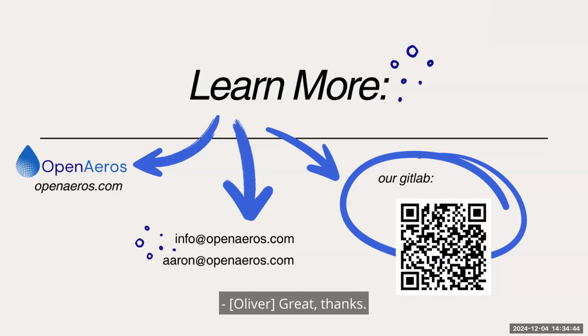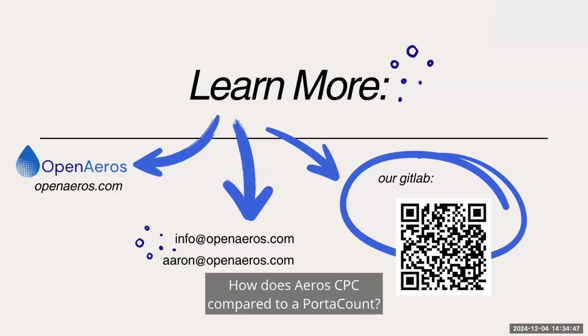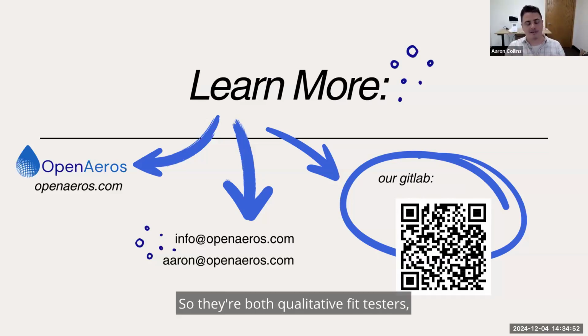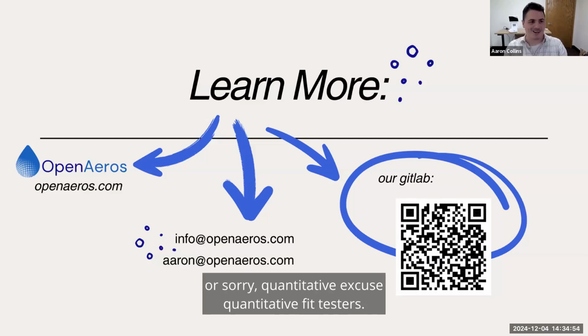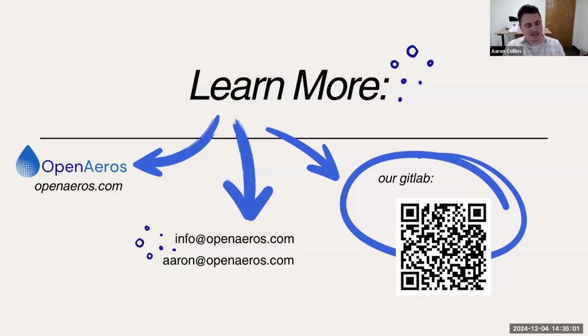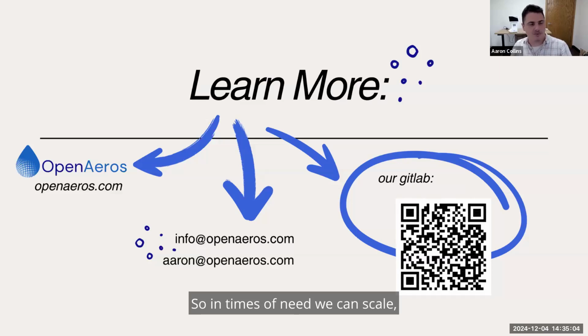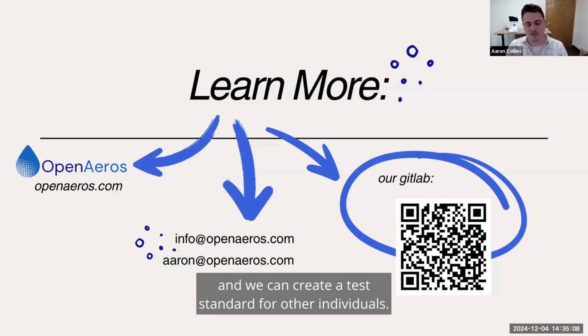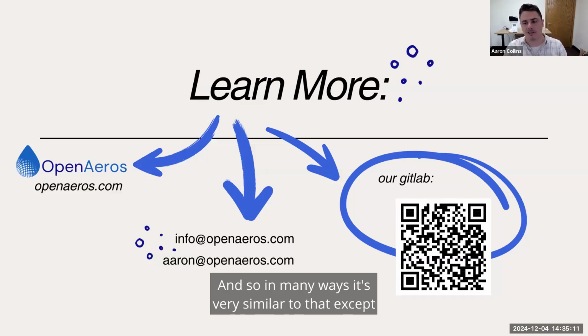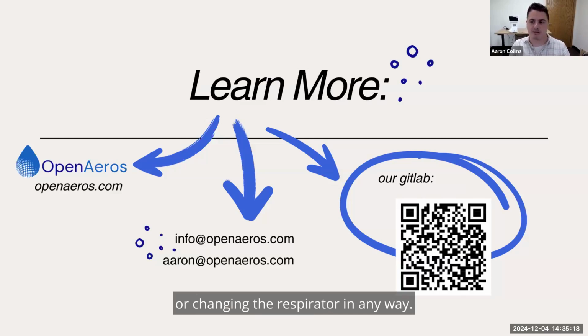How does the Aeros CPC compare to a PortaCount? They're very similar. They're both quantitative fit testers, so they measure the particle concentration inside and outside. The big advantage to ours is that it's a lot lower cost. It's also open source, so in times of need, we can scale, other manufacturers can produce them, and we can create a test standard for other individuals. It's also different because of this new probe technology, which allows you to do it without modifying or changing the respirator in any way.